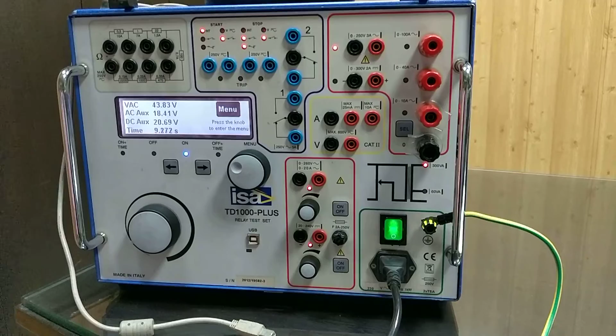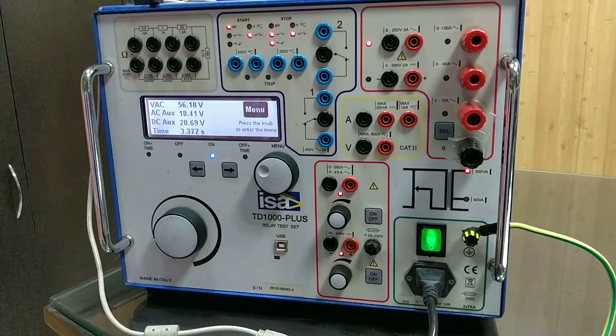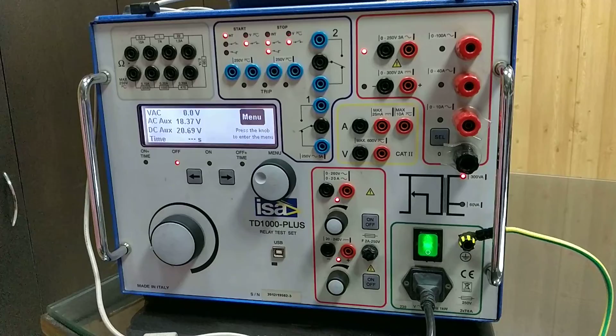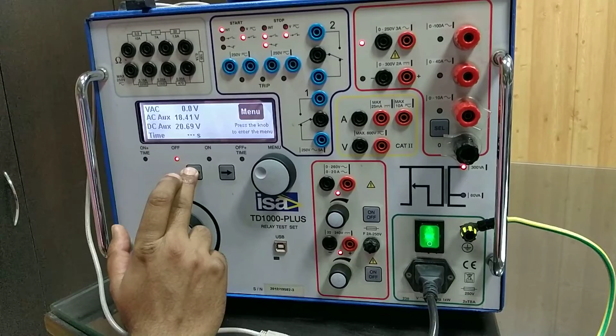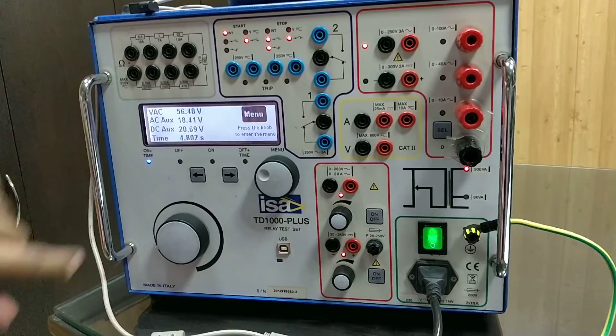So we are showing an example of how to measure the trip time by using TD1000 plus. In this, let's assume we have generated some amount of voltage, like 56.18. Now we have just switched off, and then we have put it on pulse time, because pulse time is mainly designed to measure the accurate timing for a particular generation. Without changing the knob positions, now we are selecting the pulse time, and now in the display we are generating the same voltage again, as well as the timer is started.